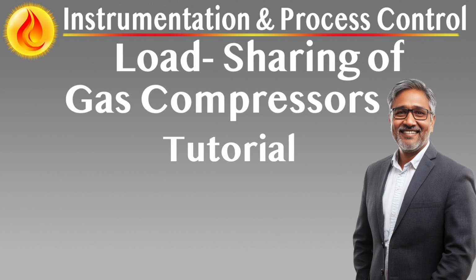2. Recycling operation, reduced throughput needed. The anti-surge controller at each compressor multiplies CRSC by its load sharing gain. This signal is added to the surge control response to raise the recycle flow rate. Load sharing controllers become passive for capacity modulation in this state. This bifurcation ensures that only the most appropriate actuator, recycle valve, or speed set point is used for flow adjustment, preserving surge margins and reducing mechanical wear.